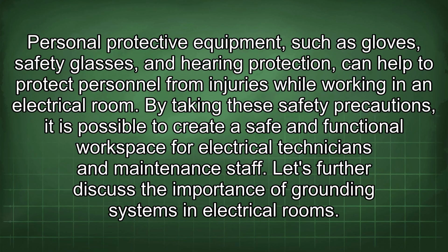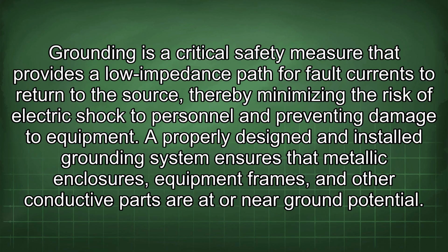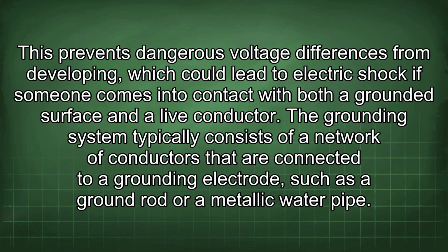Let's further discuss the importance of grounding systems in electrical rooms. Grounding is a critical safety measure that provides a low impedance path for fault currents to return to the source, thereby minimizing the risk of electric shock to personnel and preventing damage to equipment. A properly designed and installed grounding system ensures that metallic enclosures, equipment frames, and other conductive parts are at or near ground potential. This prevents dangerous voltage differences from developing, which could lead to electric shock if someone comes into contact with both a grounded surface and a live conductor.